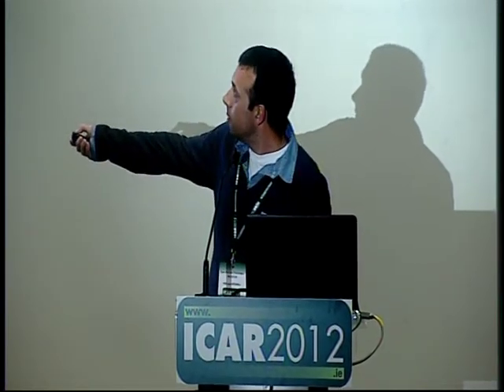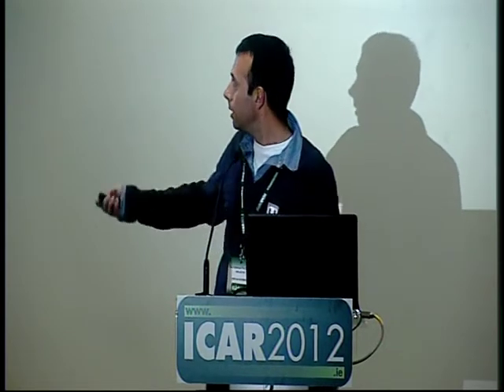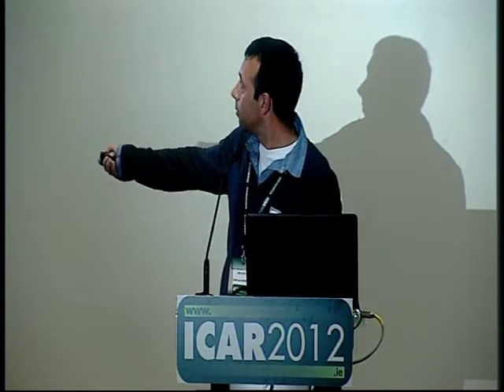But here, you cannot see it maybe very well, you still have a lot of differences. Maybe I can make it bigger. Before standardization, I still have differences between the spectra coming from Bentley and those coming from FOSS. After the standardization, if I apply my PDS, I get something like this. Now you cannot see any difference between a FOSS instrument or a Bentley instrument. So now you can be sure that what you are measuring is exactly the same as in the FOSS.